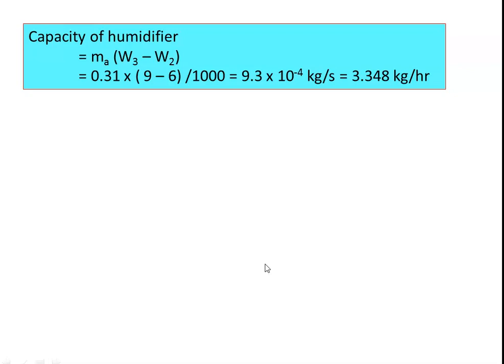The capacity of the humidifier — the amount of water vapor added — is: Ma (W3 − W2) = 0.31 × (9 − 6) / 1000 = 9.3 × 10⁻⁴ kg/s, or 3.348 kg/hour.